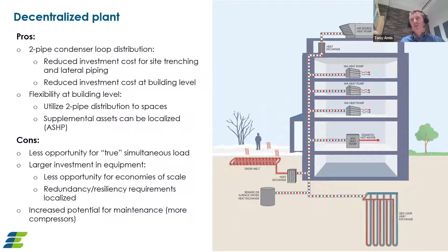Over the 20 years we've been designing these systems, we would never design a system to deliver all of the heating and cooling from geothermal alone, purely because if you try to design a system to meet peak loads, you'll end up with probably three times the size of bore field you really need. And when you go back to the developer and tell him what that's going to cost, he's probably going to say thanks, but no thanks.